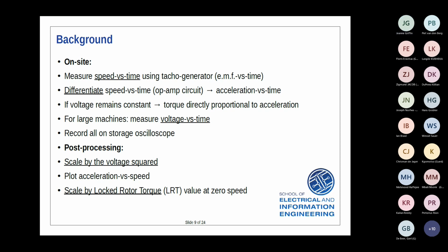And what's also important, if the voltage remains constant, then we've got a pretty good relationship between the torque and the acceleration. But what we found is that for larger machines, because they're being tested only by a generator which doesn't have infinite bus bars, the voltage regulation is quite difficult. And as you know, the torque being proportional to the voltage squared, any fluctuation in the voltage has a significant effect on the torque. So for the larger machines, we actually measure the voltage as well. Record it all on the storage oscilloscope. And then when we get back to the university, we do some processing. We scale our measurements by the voltage squared. It's very important to keep the voltage constant. And then plot the acceleration versus speed. And then we scale it by the locked rotor torque value, which is at 0 speed, obviously. And that's normally provided by the manufacturer.